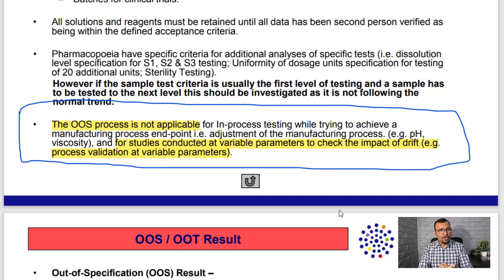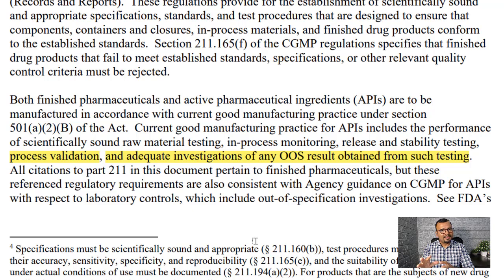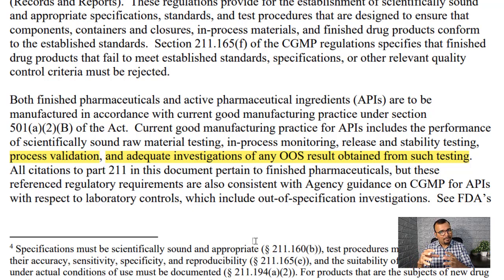This is the reference from the UK MHRA presentation. Now, when I refer to the US FDA guidance document on OOS, the FDA has not — according to my knowledge — mentioned the same point as MHRA. As you recall, MHRA said that investigation may not be required under the OOS process for out-of-spec results found with variable parameters.